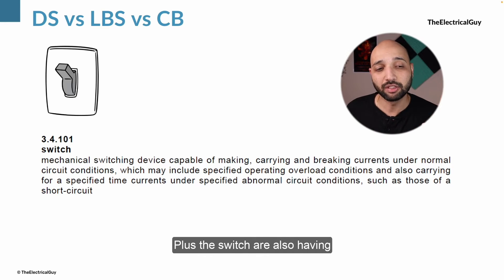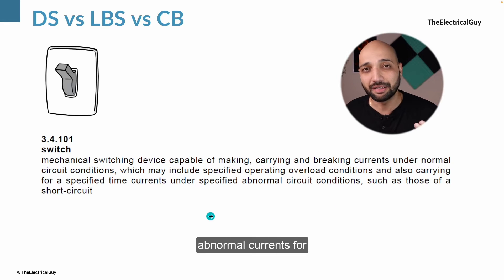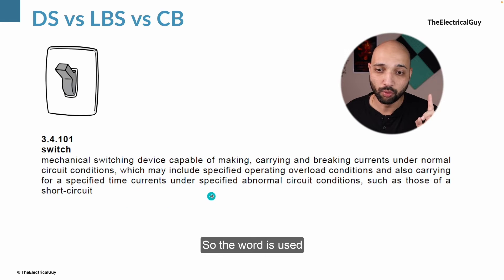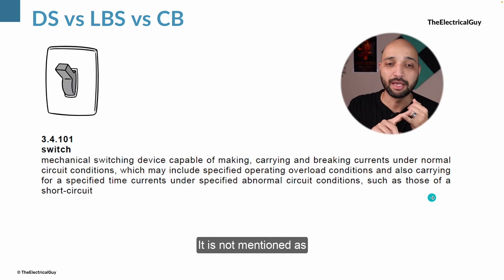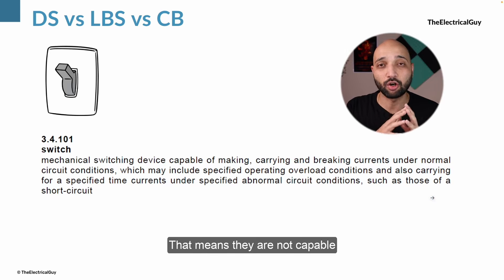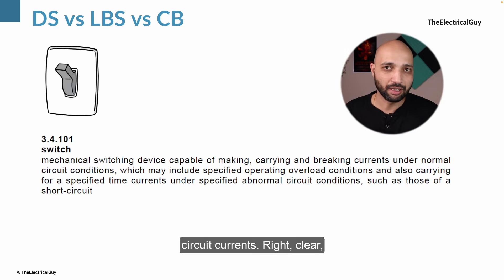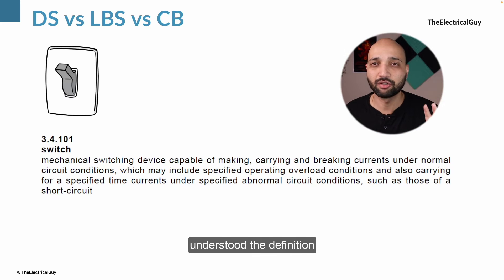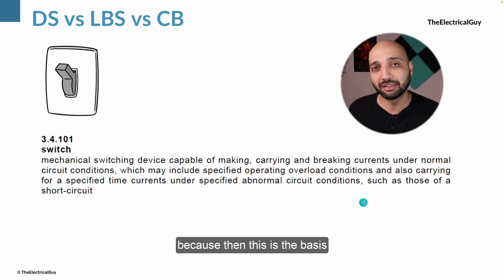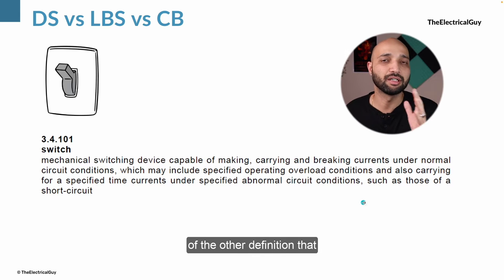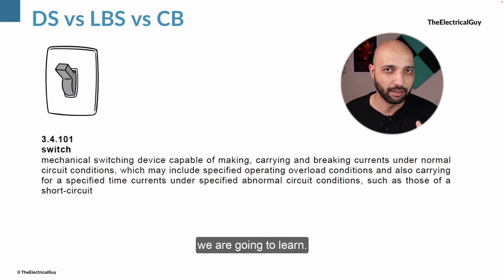Additionally, switches also have the capability to carry abnormal currents for a specified time. The key word is 'carrying' only — it is not mentioned as making or breaking, which means they are not capable of making or breaking short circuit currents.